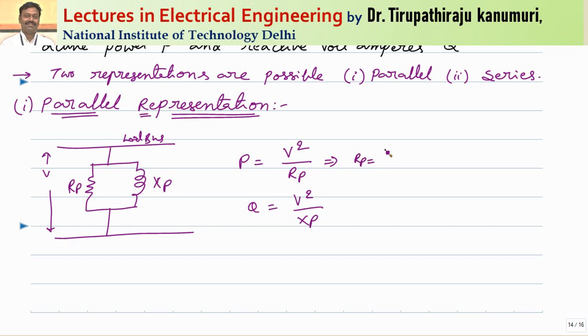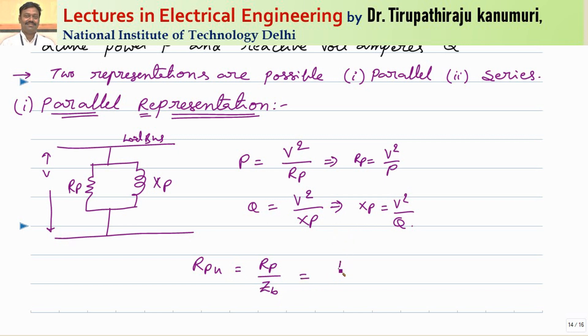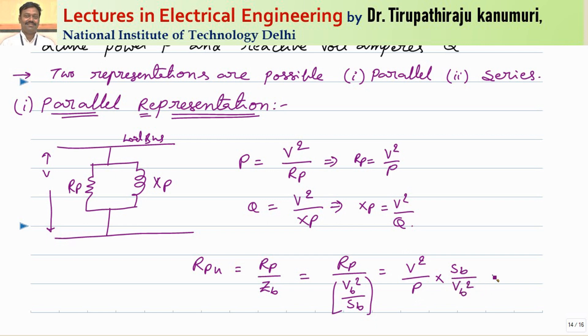From this, I can write rp equals V squared divided by P, and xp equals V squared divided by Q. So the per unit value of r can be calculated as rp divided by the base impedance, where base impedance equals V_base squared divided by S_base. Substituting the value of rp, this becomes V squared over P multiplied by S_base over V_base squared. The ratio V over V_base becomes V per unit, so this gives r per unit equals V_pu squared times S_base divided by P.